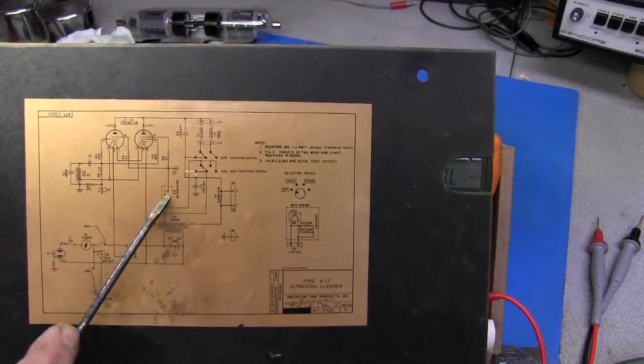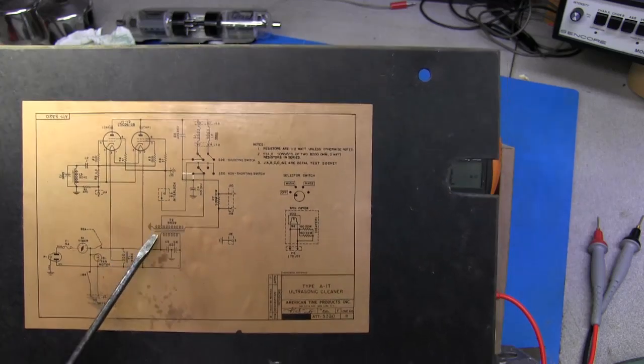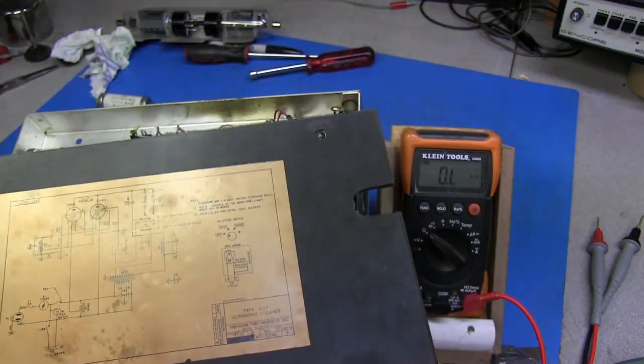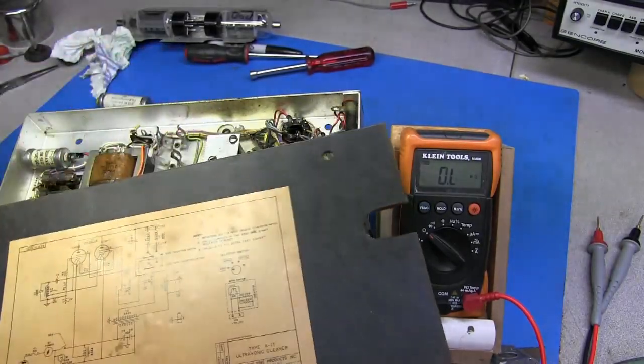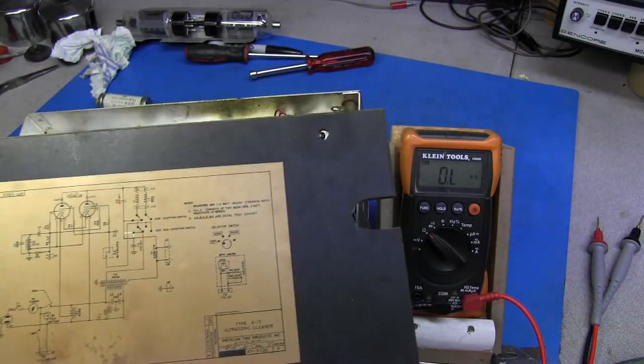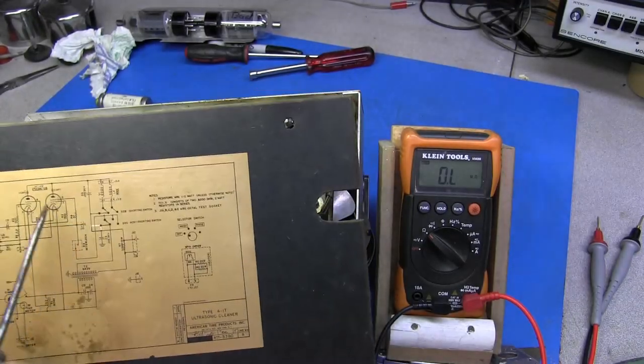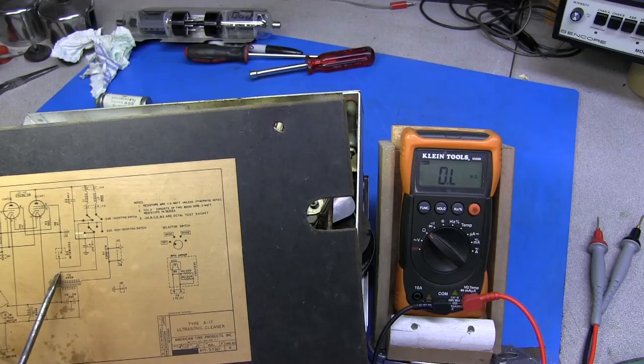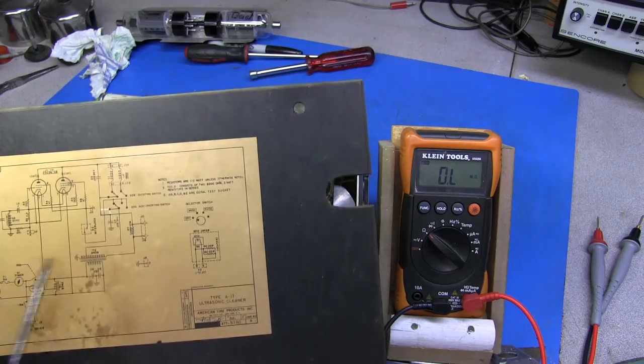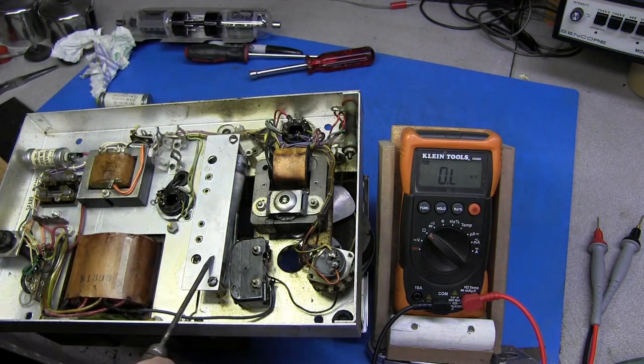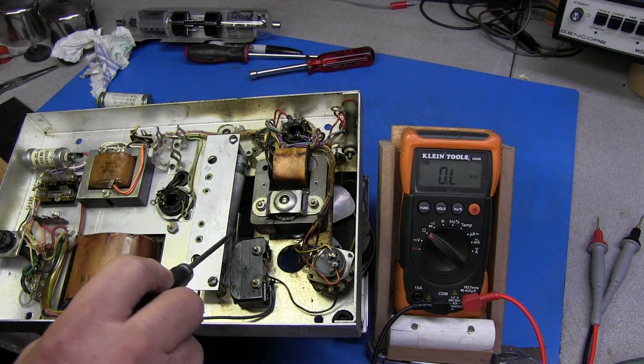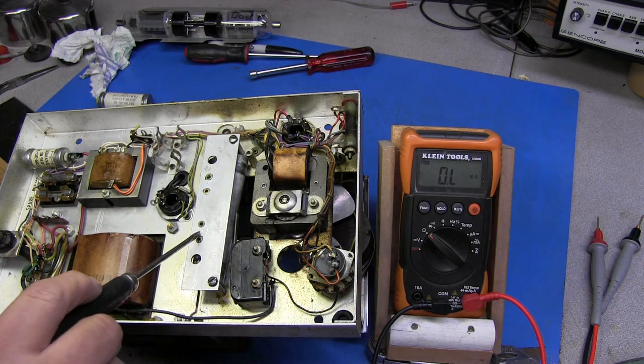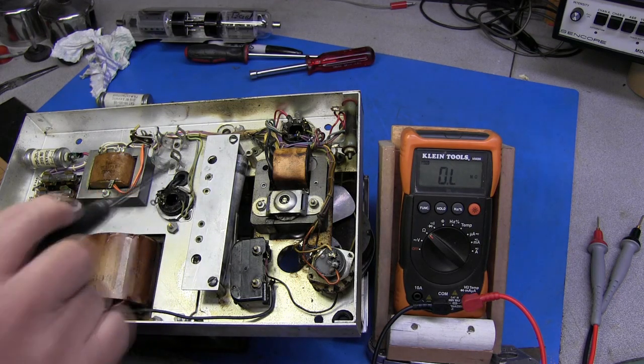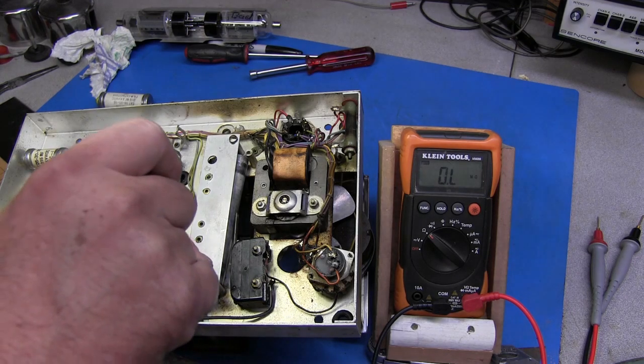You can see here it says interlock. So when you got the cups out, it actually shuts the high voltage off to the tubes. And the way this works is that when those cups come in, they contact a cylinder that pushes a micro switch in, and also makes contact to ground through these bars here, and I'll show you exactly how that works.